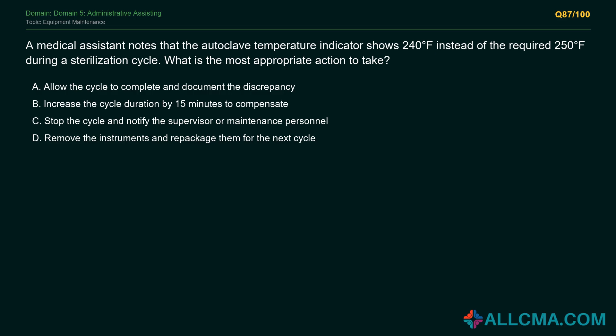The correct answer is C. Autoclave sterilization requires a minimum temperature of 250 degrees Fahrenheit, 121 degrees Celsius, at 15 psi for 15 to 30 minutes to achieve proper sterilization. If the temperature indicator shows a lower value, sterilization cannot be confirmed and instruments are not safe for patient use. The cycle must be stopped and equipment malfunction must be reported immediately.